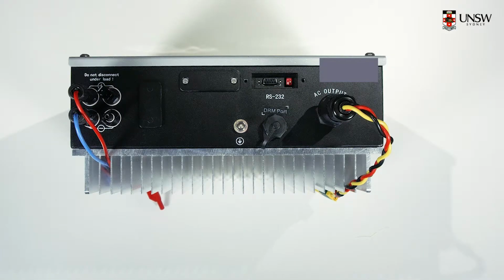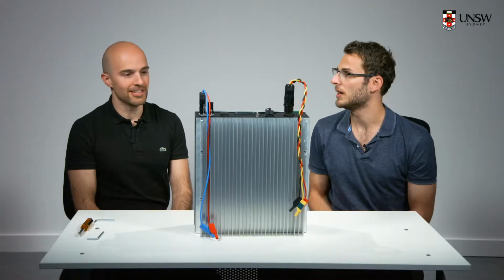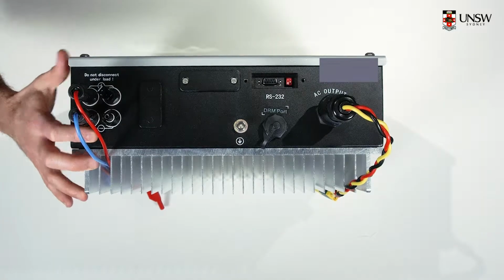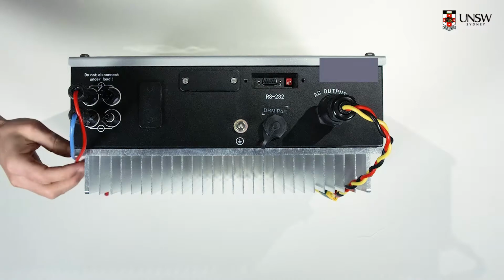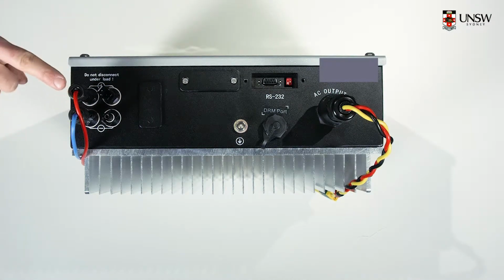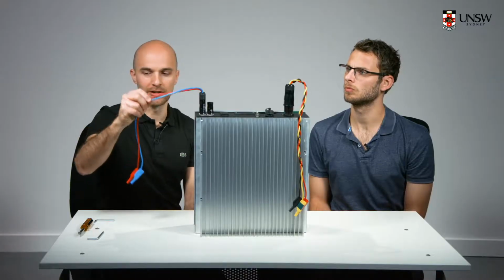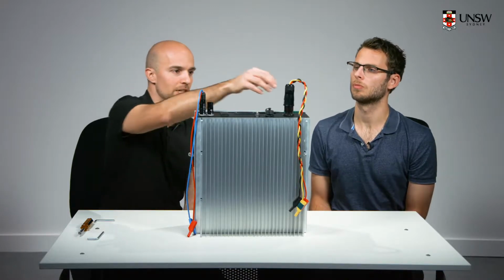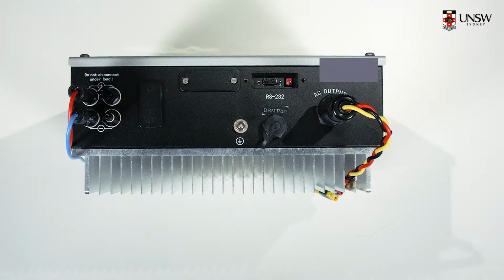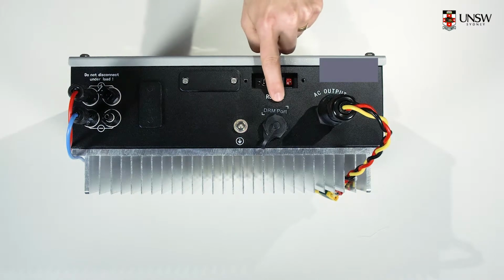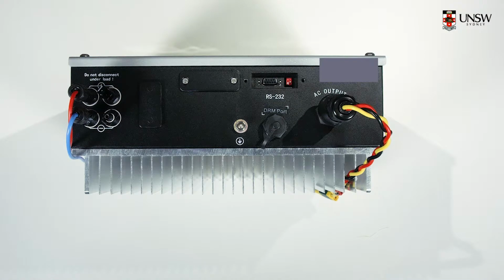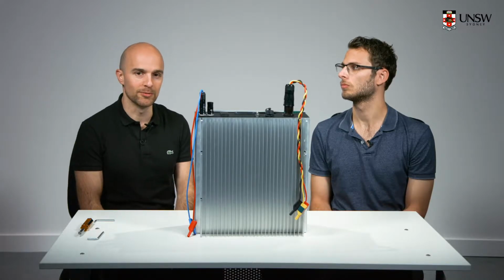Let's get started with the top panel. This is the top panel where we connect the electricity and the input from the solar arrays. On this side we have two DC inputs, which we can recognize from the color of the cables, one red and one blue. We have an output here on the other side, the AC single phase output. Then we have some communication ports: the RS232 to program the inverter, and another port called DRM, the demand response management port, which is for the grid operator to decide whether the inverter needs to remain turned on or off in case there are problems in the grid.